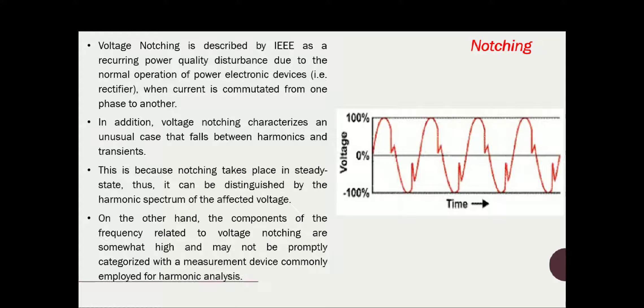Hello everyone, welcome to the power quality lecture series. In this video we are going to discuss one of the reasons of voltage or waveform distortion, that is notching. Voltage notching is described by IEEE as a recurring power quality disturbance due to the normal operation of power electronic devices, like a rectifier. When current is commutated from one phase to another, there will be voltage notching.